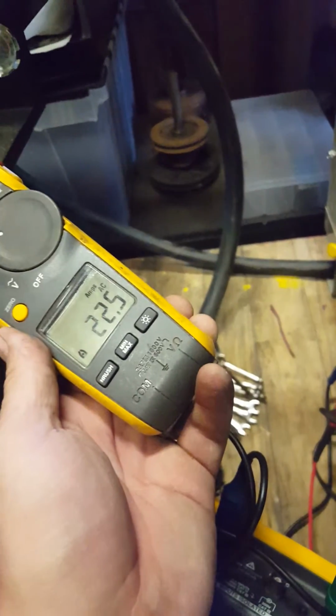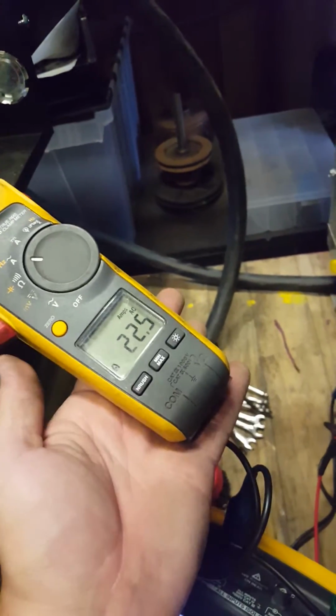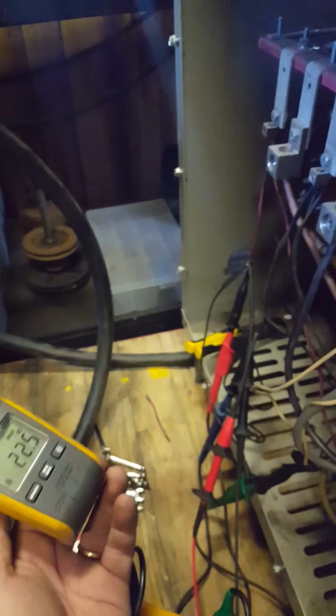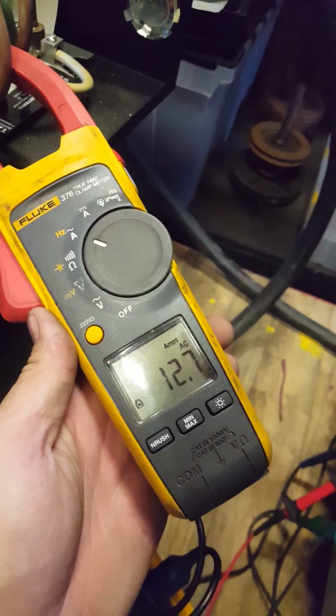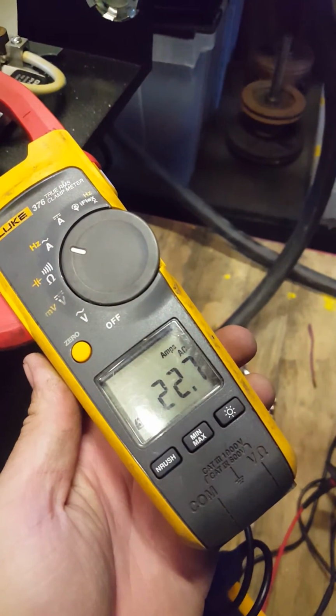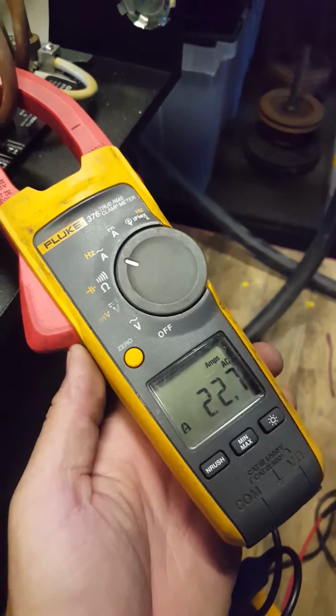Alright, now let's see what happens when I kick on this motor. Measure the single phase amps again. Oh, our amps went up a little bit. 22 amps on the single phase, just running this transformer. Alright, let's turn the transformer off. 12 amps. 22. The transformer has a pretty high quiescent current, which I guess makes sense being a 30 kVA transformer.